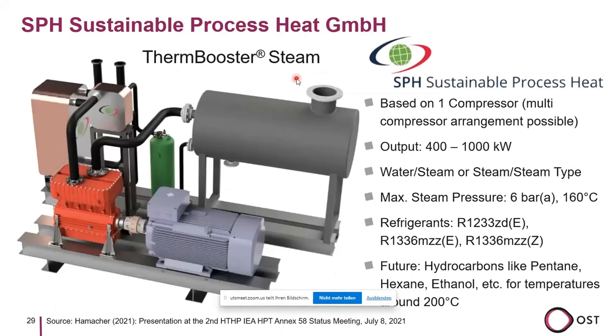When you speak about steam generating heat pumps, there are some suppliers. One is SPH, Sustainable Process Heat, from Germany. They have this system here, 400 to 1000 kilowatt based on one compressor, which can run with water or steam, up to 6 bar, and the refrigerants used are the hydrofluoroolefins, depending on the required steam pressure or temperature. And there are options for future fluids.